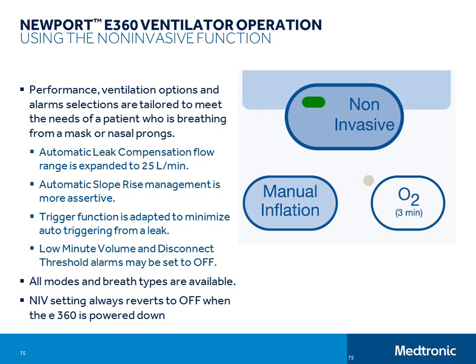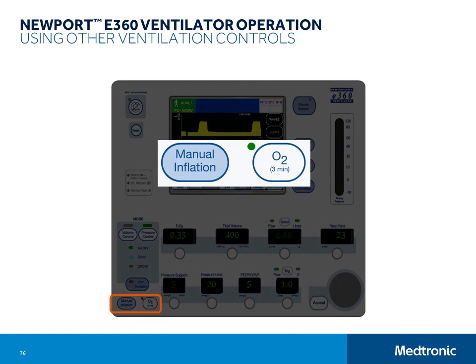There are two commonly used controls that are found on the control panel in the left lower corner. They are the manual inflation button and O2 3-minute button. To perform a manual inflation, push and hold the manual inflation button, then release the button to end inspiration and allow exhalation. To initiate a 3-minute O2 function, which delivers 100% oxygen to the patient for 3 minutes, just push the button. This button has a toggle function. To end the 100% O2 delivery before 3 minutes have elapsed, you can push it again. It is lit when active.